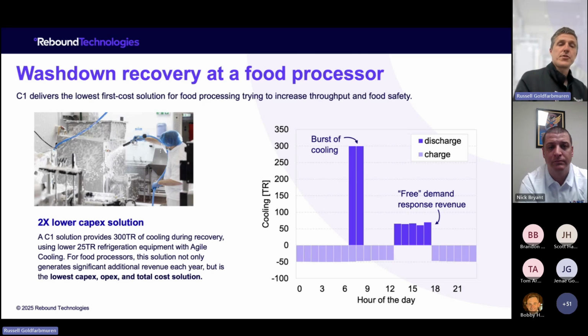So here, what we're able to do is run for almost all the hours of the day, give them some free demand response in the middle of the day, just as a kicker, and then we deliver all of our cooling in these 2 hours at the beginning of the day to recover from washdown. So this gives the facility back 2 hours of operational time every day. Obviously, that's a huge value, and we're able to do that at a much lower CapEx because of this agile cooling trait of our technology.